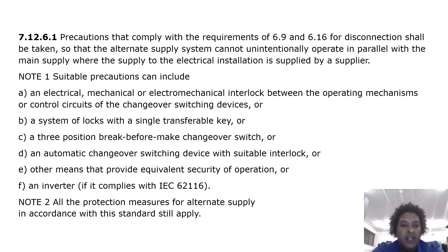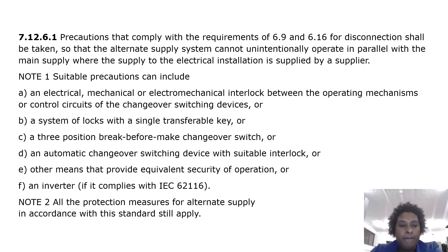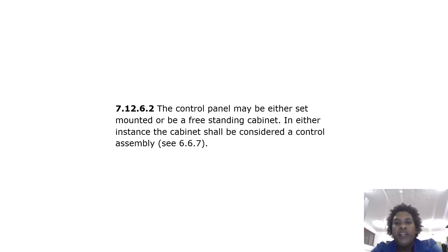Further suitable precautions include: a three-position break-before-make changeover switch; an automatic changeover switching device with suitable interlock; other means providing equivalent security of operation; or an inverter complying with IEC 62116. Note: all protection measures for alternate supply in accordance with this standard still apply. The control panel may be either set-mounted or a freestanding cabinet; in either instance the cabinet shall be considered a control assembly.